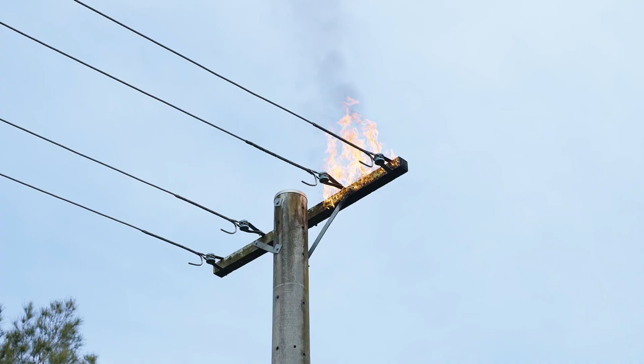In order to safely extinguish the fire, you should park all vehicles at a safe distance, stand back, and keep others at least 8 metres away. Use vehicle-mounted pumps and pulse the stream above the pole. Do not spray water directly onto the crossarm, as water is a conductor of electricity. Use a nozzle that breaks the water stream by 50% and allows oversprayed water to put out the fire.